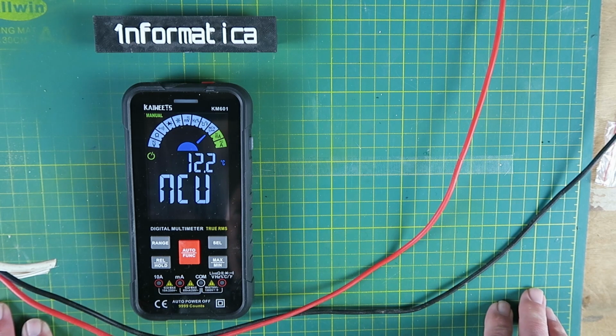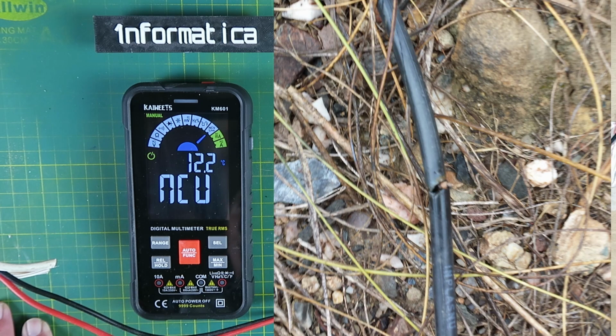Where I live in the south of Spain, things like health and safety and the difference between live and neutral are rather vague concepts. I was asked to investigate why something wasn't working in an outside pump room, to find that ordinary mains wiring strung along the ground for some 100 meters, and at some point a rodent had a good old chew on it. It wasn't until it rained that the whole thing shorted out. Being able to go along a cable and find a fault, even when it's not as obvious as this one, has got to be useful.